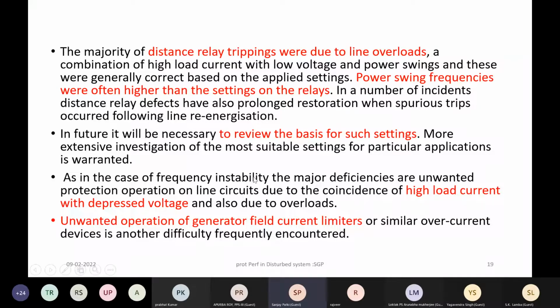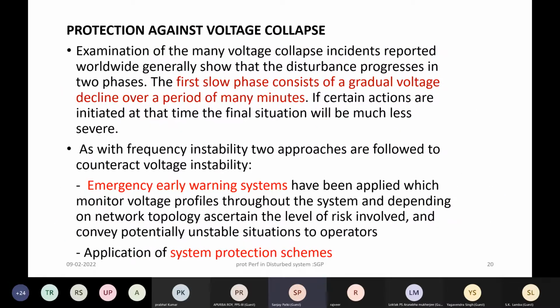How do we avoid distance relay tripping due to line overload during emergency loading? During emergency loading, there will be high load currents with low voltage, and there could be power swings. So how can this tripping be prevented in such a contingency when the system disturbance is there? So that was the main summary recommendation as far as protection is concerned.